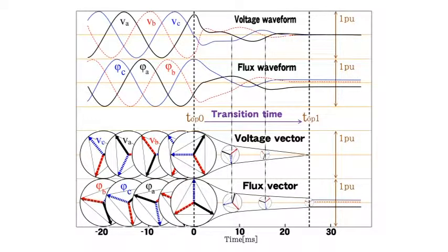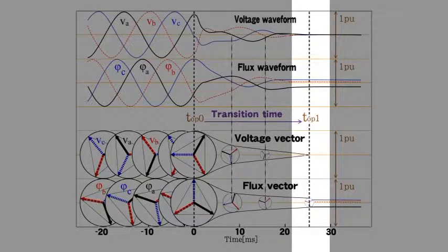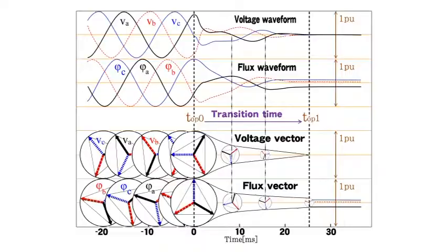In other words, Koudensha has successfully proven through testing and theory that the fluxes at T open 0, which occur immediately after tripping, are not the real residual fluxes. The real residual fluxes are the ones that converge as a transit phenomenon at T open 1.